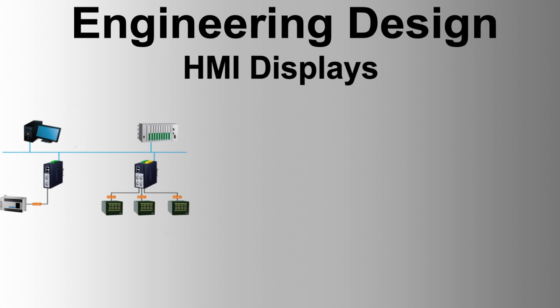Backup of system files shall be made whenever changes to the system are implemented following a software change. A procedure on maintaining backup media, e.g., number of copies, last date of backup, and storage location shall be developed. System documentation shall be available. Security and access rights shall be documented. Software copies of graphics shall be available.